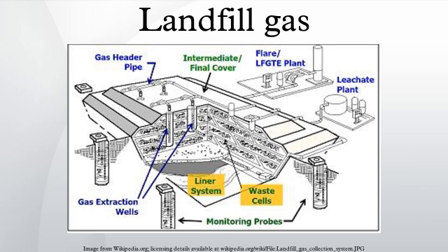Monitoring. Some of the gases produced by landfills are hazardous and monitoring techniques have been developed. Flame ionization detectors can be used to measure methane levels as well as total VOC levels. Surface monitoring and subsurface monitoring as well as monitoring of the ambient air is carried out.